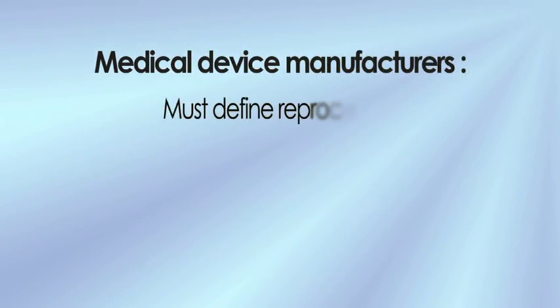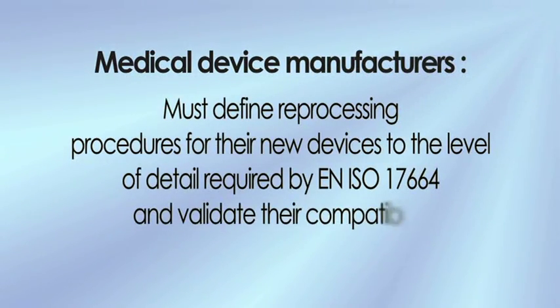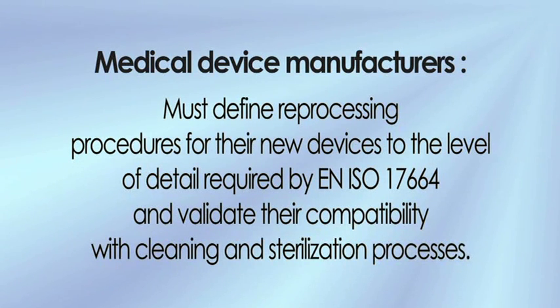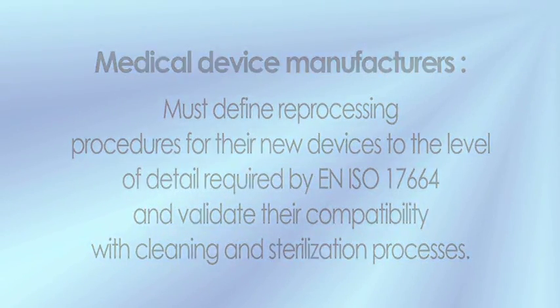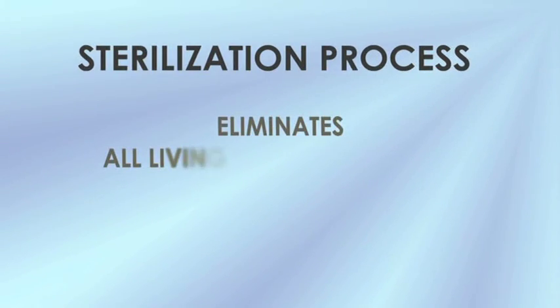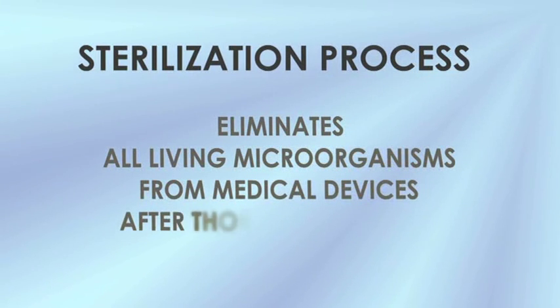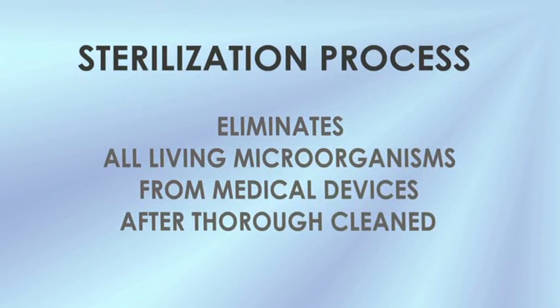Before putting a new reusable medical device on the market, the manufacturer must define a reprocessing procedure with all the details required by EN ISO 17664 and validate this procedure. The sterilisation stage must eliminate all living microorganisms from medical devices after thorough cleaning.